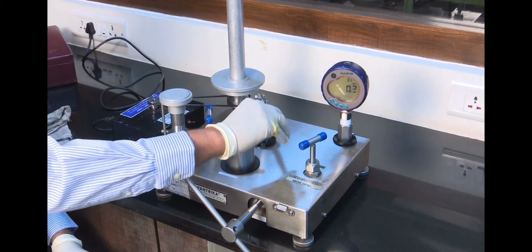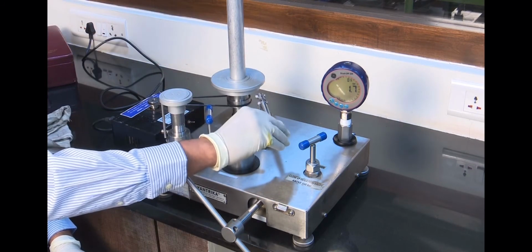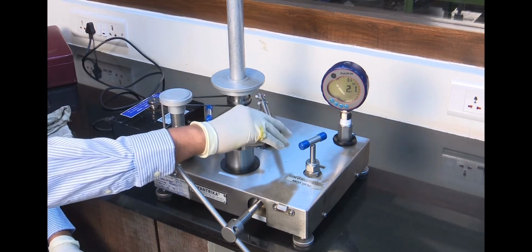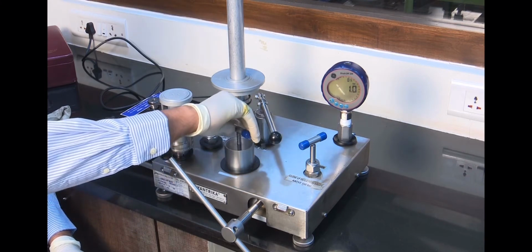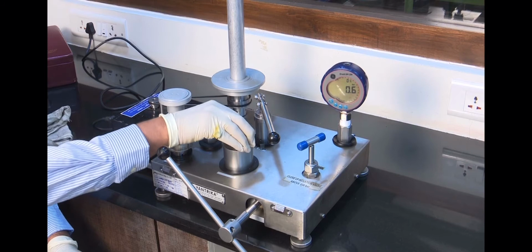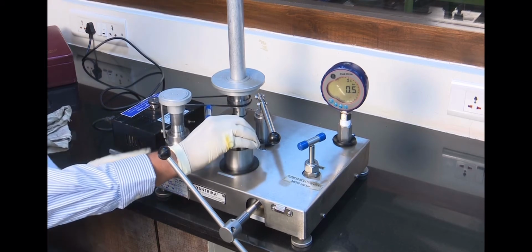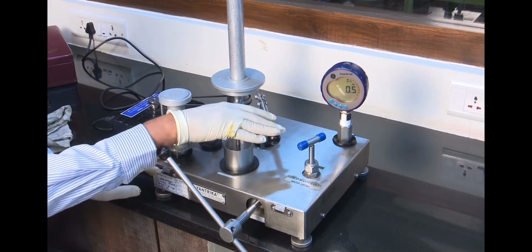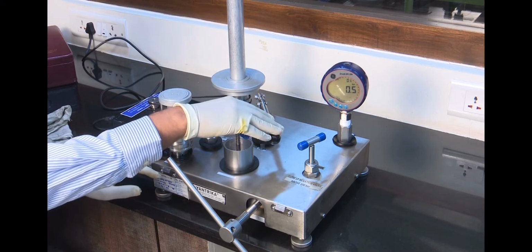Now operate priming pump lever several times and watch the oil spouting out of standpipe until no bubbles are seen in the return oil and full flow is established. After that, close the pressure valve.